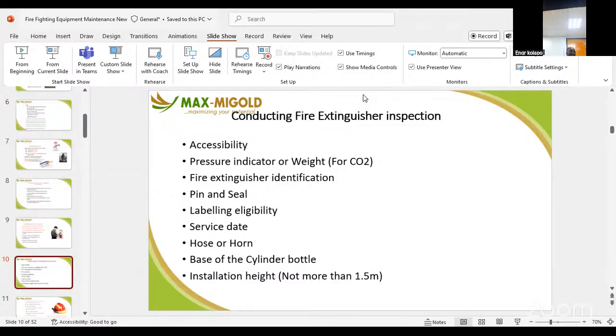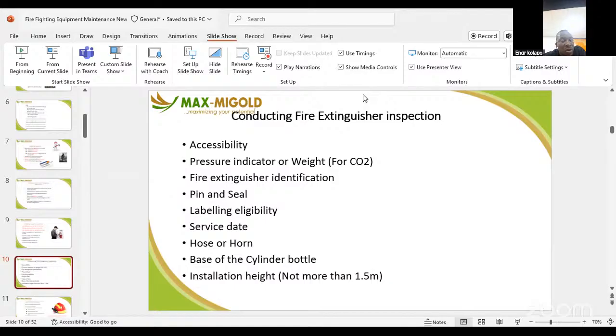Four, there must be a pin and seal by the tip or topmost part of the extinguisher. So the pin is what we're going to remove when we want to use the extinguisher. Just by the end of the hose or the nozzle, there must be a pin with a seal. Then the instructions on the extinguisher must be legible. There must be a service date to show when it was last serviced and the due date for servicing. The hose must not be defective. The bottom of the cylinder should not be corroded. Then the installation height from the floor should not be more than 5 feet, so that some of us can lift the extinguishers, if need be. Next slide.